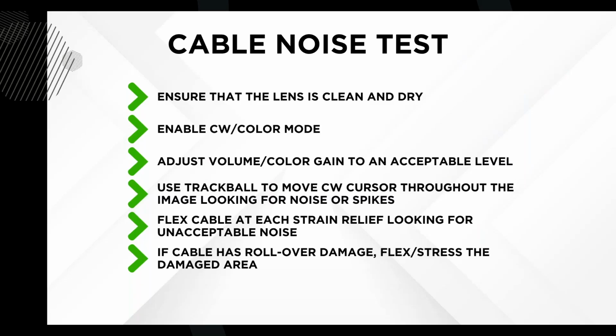Now everything looks good with the transducer, but that's one of the reasons why we typically make sure that we're flexing the cable, because there is dropout in this particular one. I don't know if you can see it. Let me crank the gain in this area. It's a little too high there, but you can see when I wiggle the cable, I'm getting cable noise there. This is an example of things that you would see when you're doing QA, quality assurance testing on transducers.